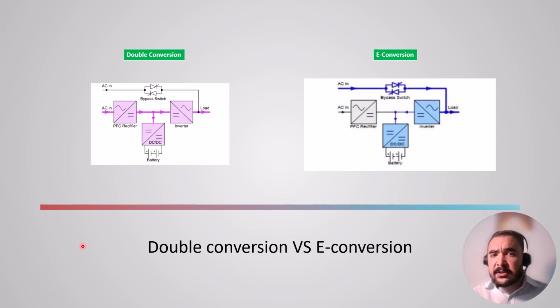Now, going back to double conversion and eco-conversion, I have to add one more thing. Many clients or partners ask if it has the same level of protection as double conversion mode. Yes, it does. In case the alternate current or main power is off, the inverter will take on in milliseconds, and your equipment will always be protected without any disruption.